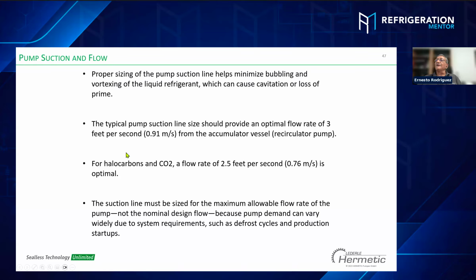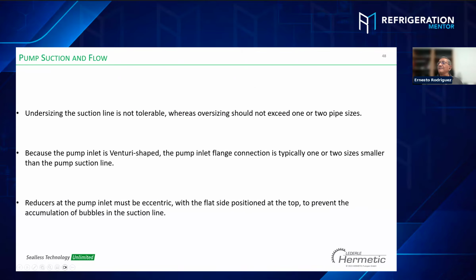Okay, basically the suction is more critical. If it is undersized, you can cause cavitation or create flash gas popping. Okay, and on the suction you are not able to exceed two sizes of pipe size according to the table we're going to show in a few minutes. Okay, don't undersize. There is no way. When you want to replace a pump or are checking a pump, make sure it's not undersized.